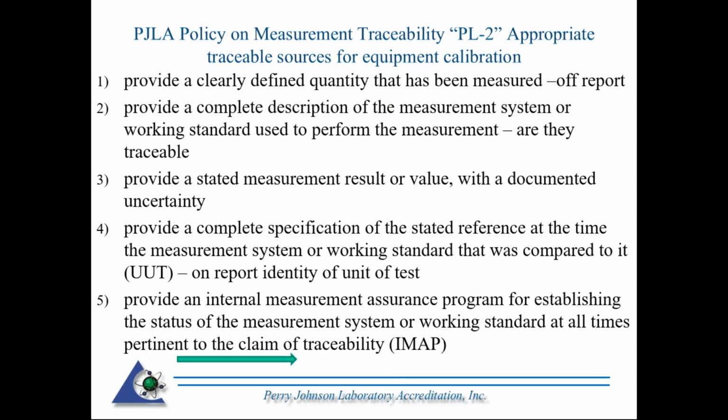and they are: ideally, the first thing we'll be looking at is the report that was provided to you. On that report should be a clearly defined quantity that has been measured, for example, the actual size. If you're doing length, for example, with a micrometer or a caliper, if it's measuring in inches or millimeters, that quantity should be specified on the report.